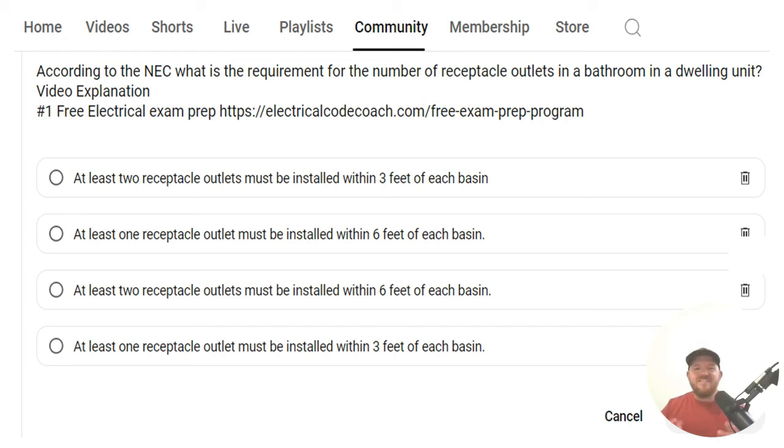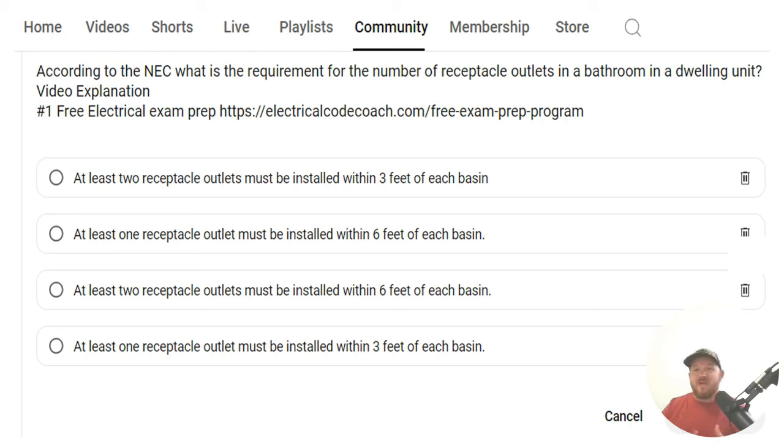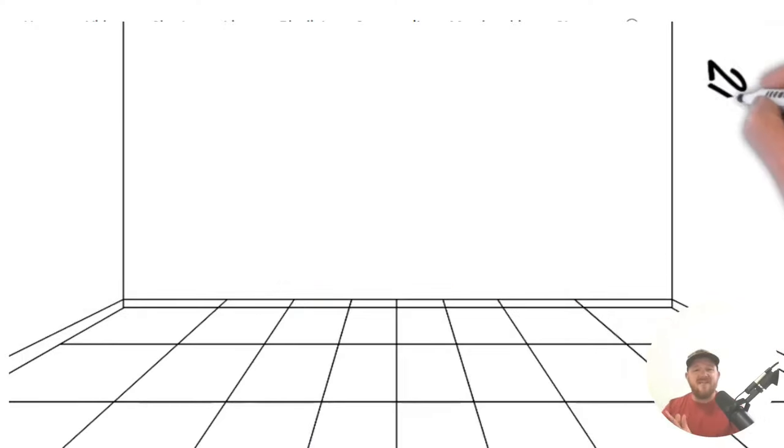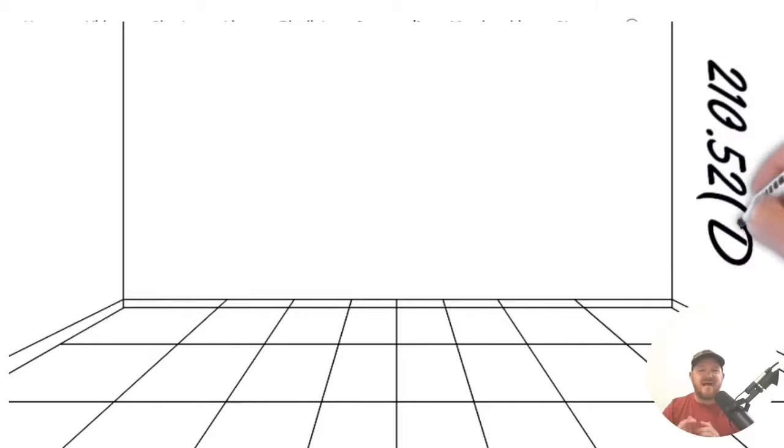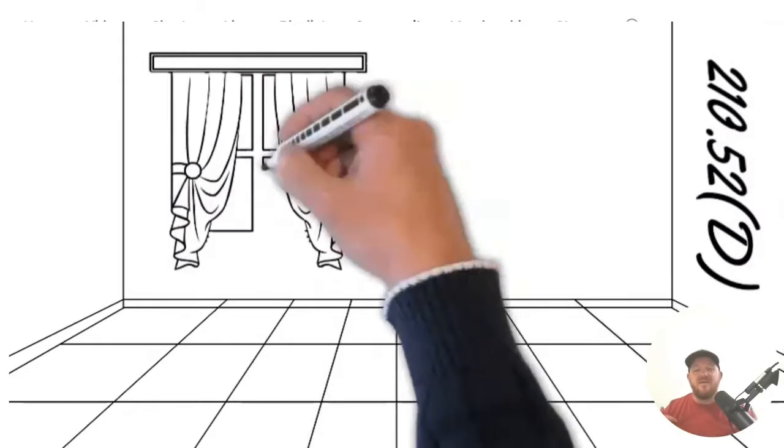According to the NEC, what is the requirement for the number of receptacle outlets in a bathroom in dwelling units? And the correct answer is D, at least one receptacle outlet must be installed within three feet of each basin. And for this one, we're going to head to 210.52D.